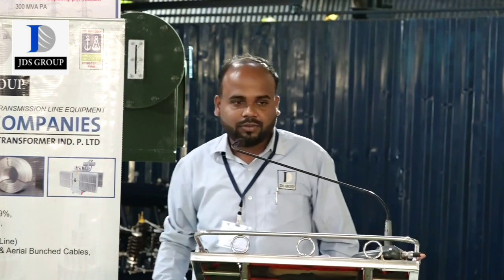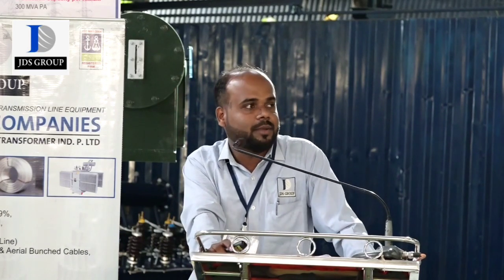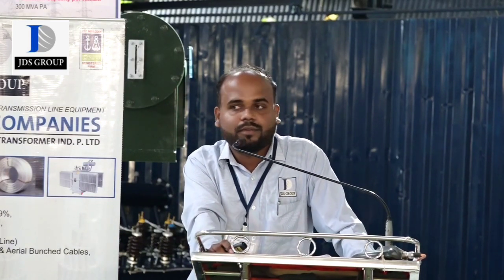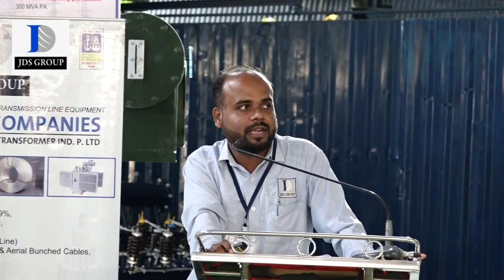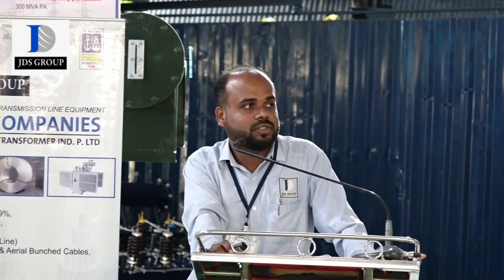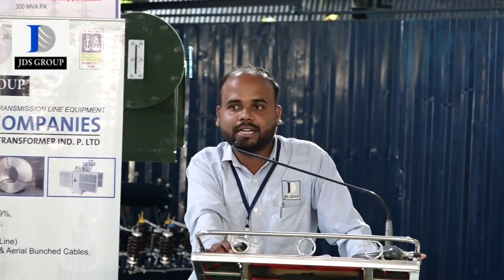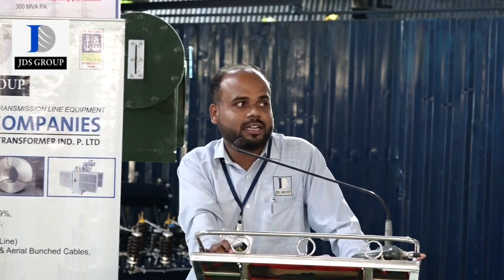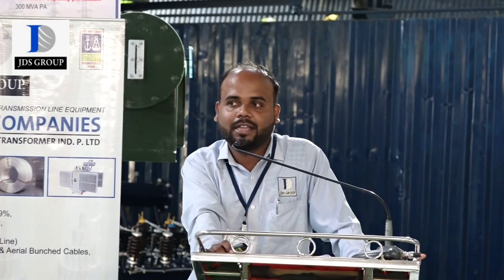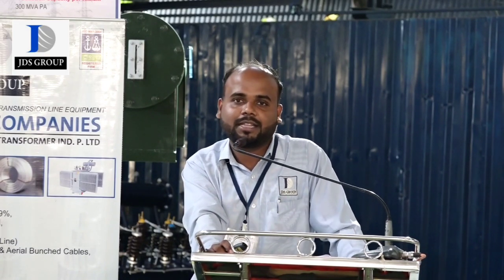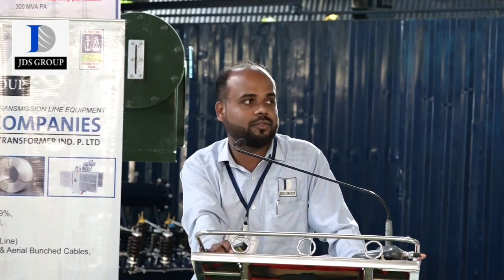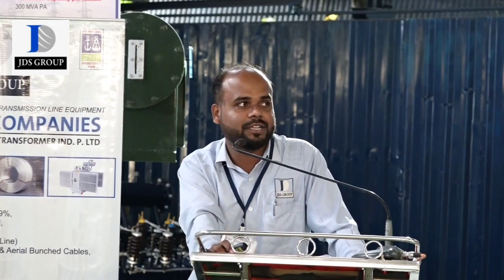So, introduction to the transformer. The main part of the transformer is core. Our core has been made up of high grade CRGO core in order to reduce eddy current losses, so that if eddy current losses increase in the core, the transformer core will get heated up. And if the transformer core gets heated up, then the efficiency of the transformer will be reduced. So we use high grade quality of laminated core.